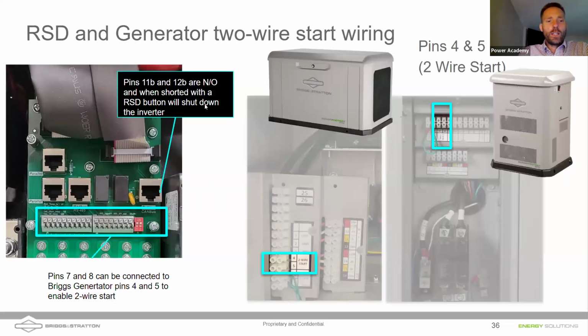If you are integrating a generator, you would want to do that with pins 7 and 8 on the control board here. There are a number of things that you use the control wires on the Sol-Ark for. A rapid shutdown is one of them. Another one is pins 7 and 8 to do the 2-wire start. This is what lets the inverter start up and stop the generator to charge the batteries as needed. On a Briggs & Stratton generator or air-cooled generators, I'm showing the 26K and the 13K power protect units, you'd want to use pins 4 and 5.